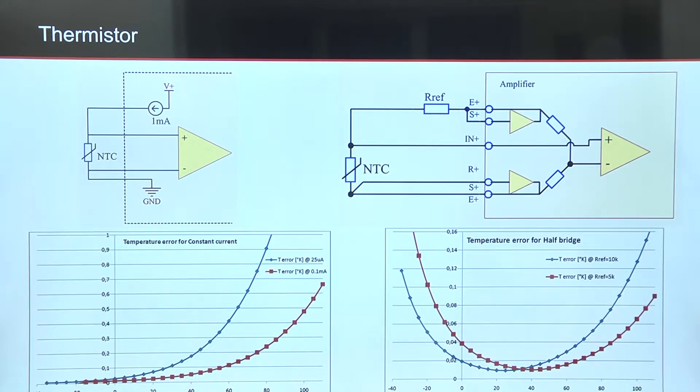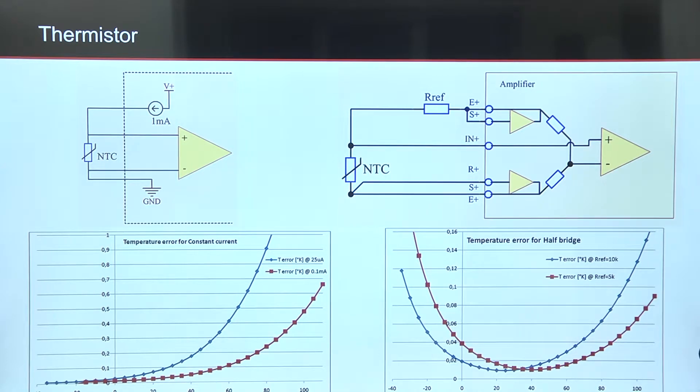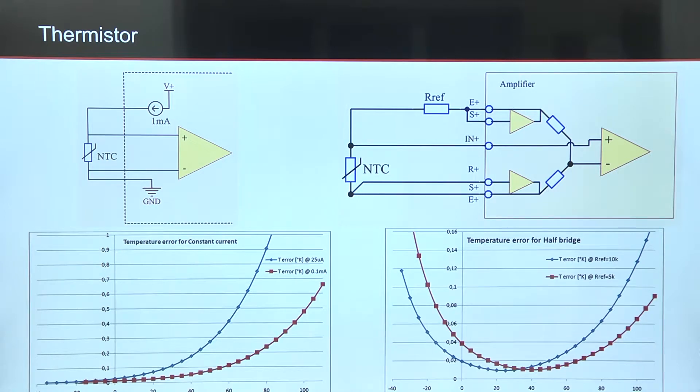First, how to connect amplifier. To minimize error, the best solution is to use half-bridge connection with external resistor, with resistance equal to nominal resistance of sensor.